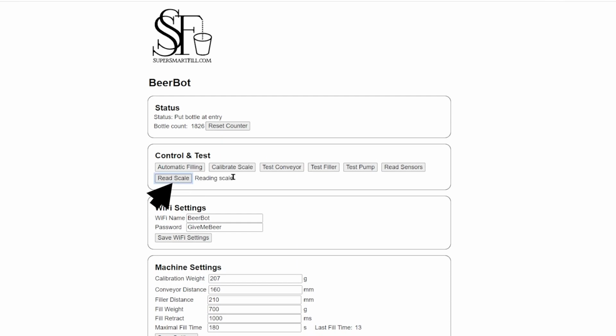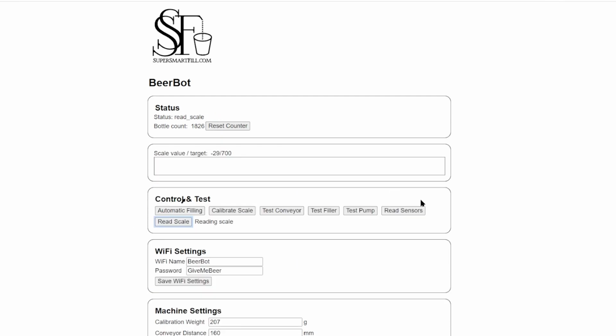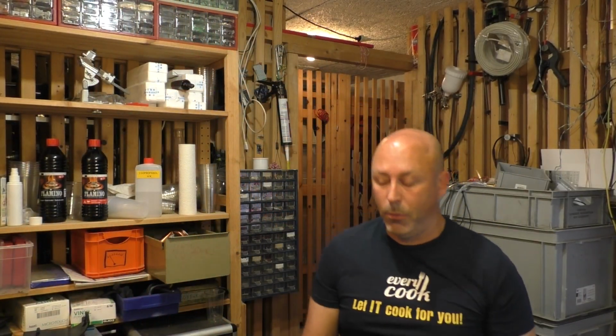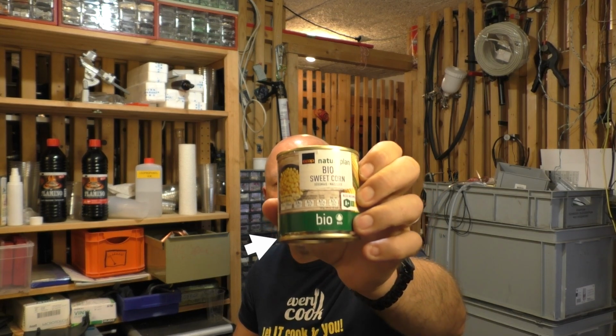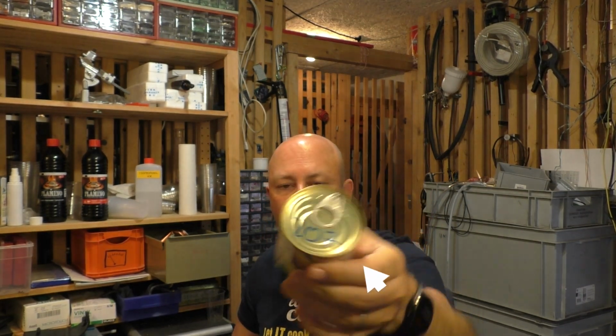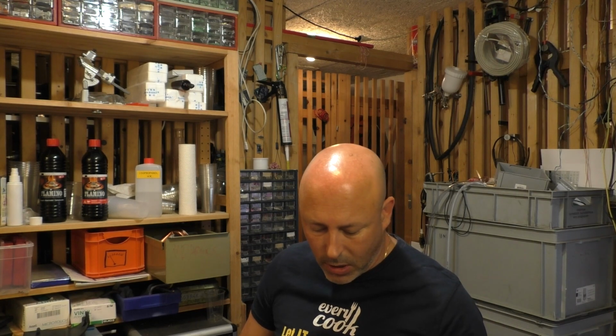So if I go to the read scale mode, you see now it is at minus 30 grams, which, yeah, okay, we need to calibrate it. Let's calibrate it. Now, I'm still waiting for my calibration weights, which I have ordered, that somehow got lost in transit. So this is my current calibration weight, and I have just marked it. It is 207 grams. It's a can of corn. But it's a reference. It's something that is not going to change for now. So to test software, it is definitely good enough.